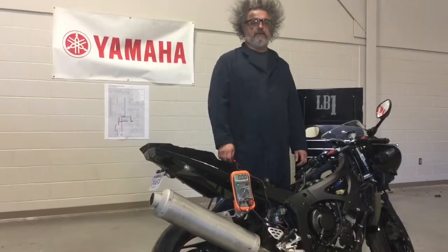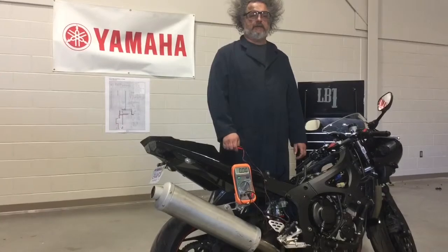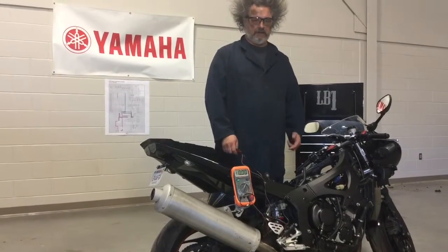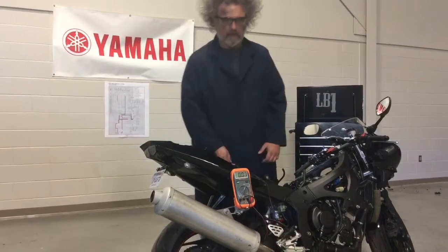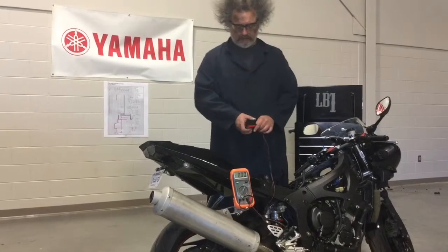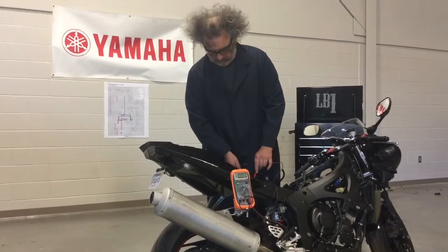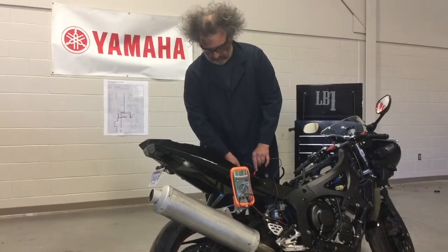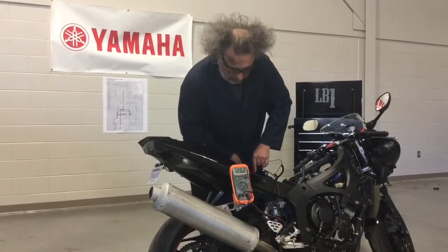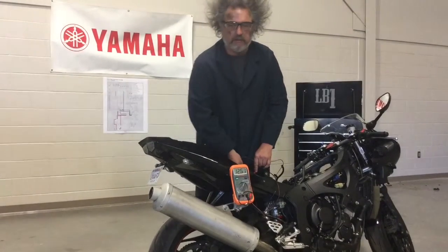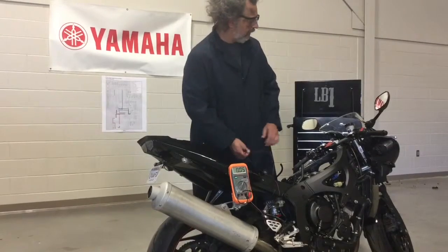Now that I have determined the fuses are in good working order, I want to check the voltage at the battery. Set the meter to volts DC, which I've already done. Now place your red lead on your positive terminal and your black on your negative. You should get a reading of 12.6, you're in good shape. That is in an unloaded state.